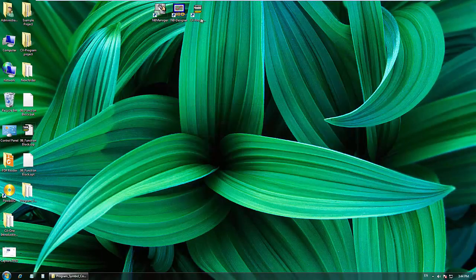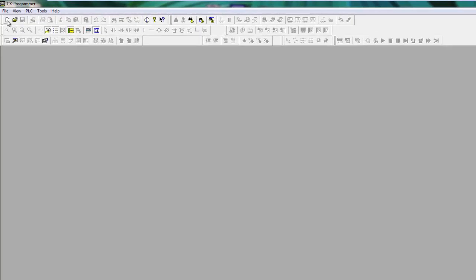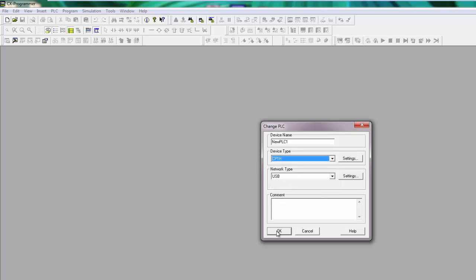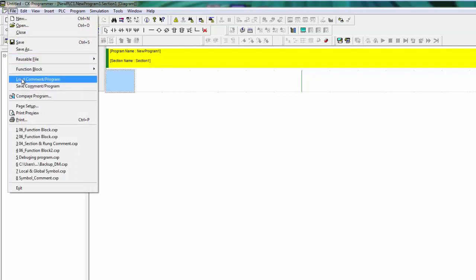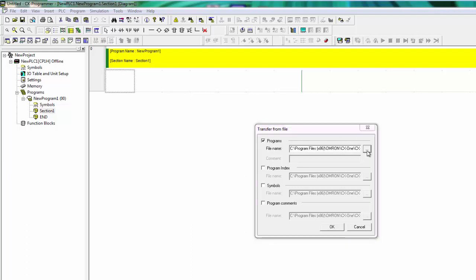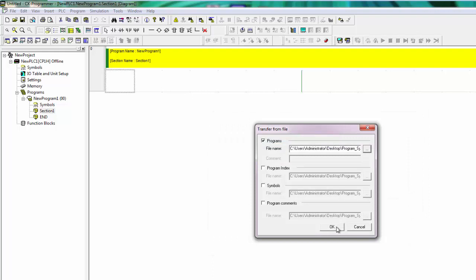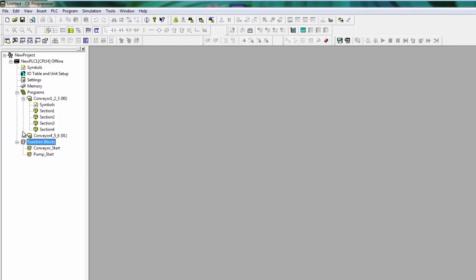All files were saved here. The first file is the PLC program, second file is PLC comment, third file is PLC index, and the last is symbol. Next, I'm going to create a new project and then import the files section by section. Open the CX Programmer, new project, select PLC — CP1H — and click OK. Next, go to File, select Load Comment and Program, first check only the program, select the file and open, click OK. Here, only the PLC program was imported.